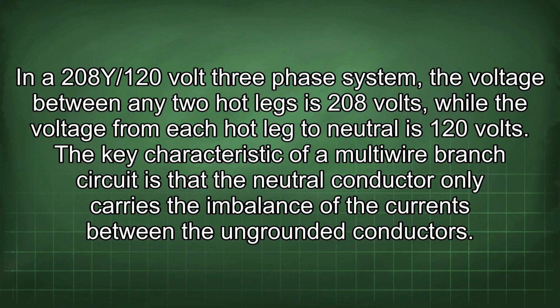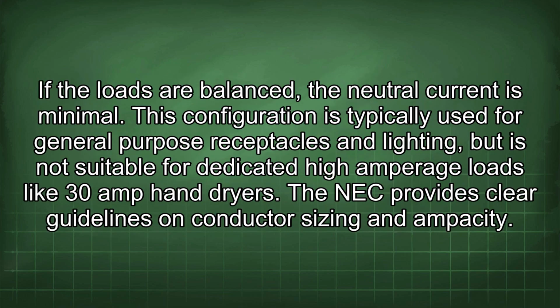The key characteristic of a multi-wire branch circuit is that the neutral conductor only carries the imbalance of the currents between the ungrounded conductors. If the loads are balanced, the neutral current is minimal. This configuration is typically used for general-purpose receptacles and lighting, but is not suitable for dedicated high-amperage loads like 30 amp hand dryers. The NEC provides clear guidelines on conductor sizing and ampacity.